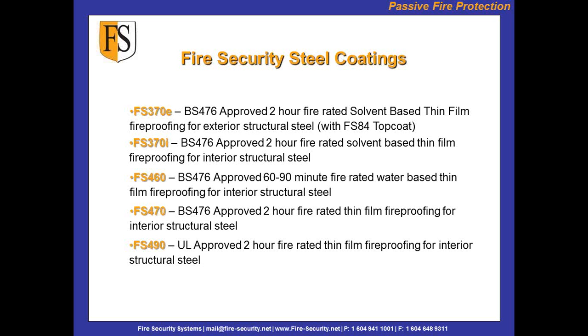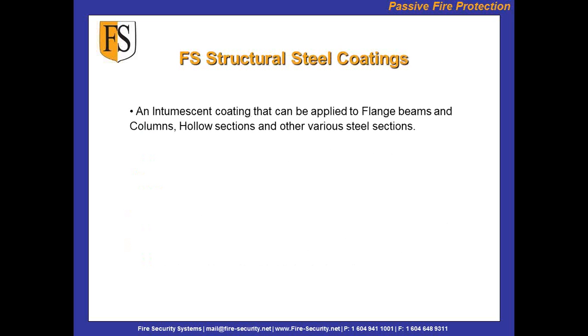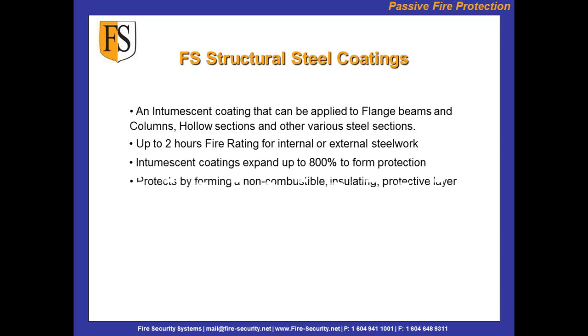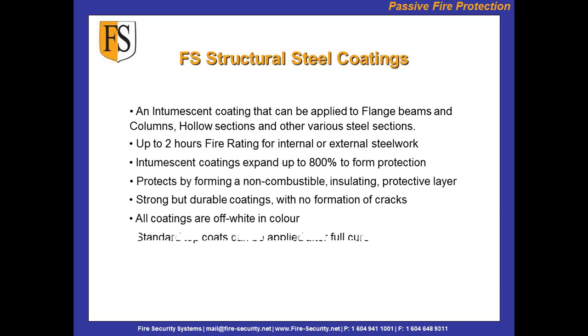Okay. So if someone wants to use FS470 for a UL-approved type of application, you will provide an engineering letter for it? Yes, we've already got one. We've already got an engineering letter that clearly states that if our British standard approved, so 370, 460 and 470, were tested under the ASTM fire curve, based on the experience they've had with the ISO fire curve, which burns higher, then they would clearly be tested in a positive mode. Okay.